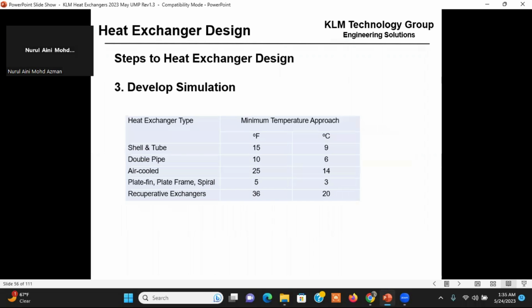Now this is out of the handbook. What are some reasonable approach temperatures? For shell and tube, maybe 10 degrees C, 15 degrees F. The problem is if you've got too close an approach temperature, the heat exchanger gets very large. So you've got to trade off between energy recovery and the cost of the capital. Shell and tube, maybe 10 degrees C, double pipes are a little better. Fin fans, maybe 15 degrees C. Plate fins 3, because remember you've got a lot more surface area in a plate fin, or a spiral, so you get within 3 degrees. Recuperative exchangers, like on a cogen, very large heat exchange transfers, maybe 30 degrees. What you want to do is get a reasonable number for minimum temperature approach so the heat exchanger doesn't get too large.